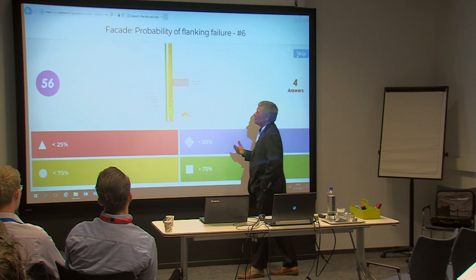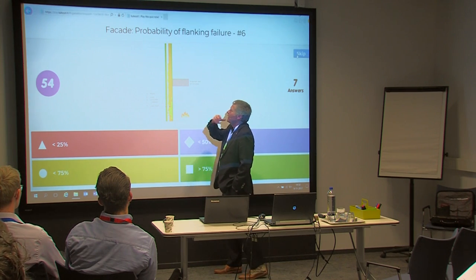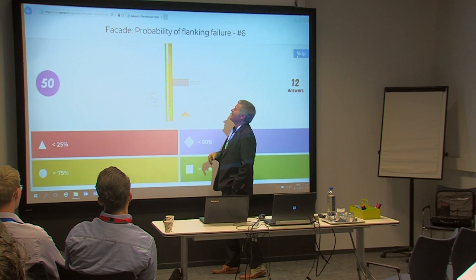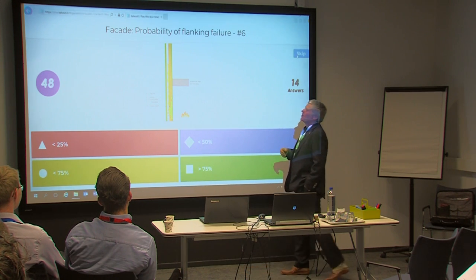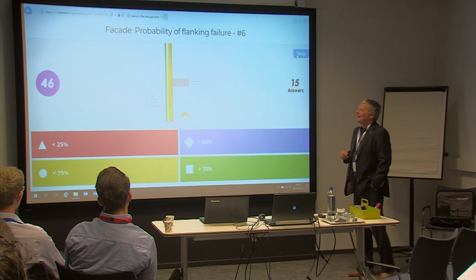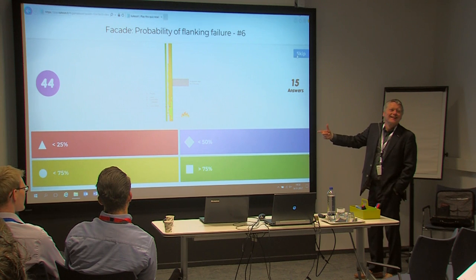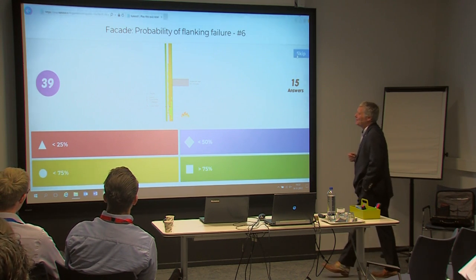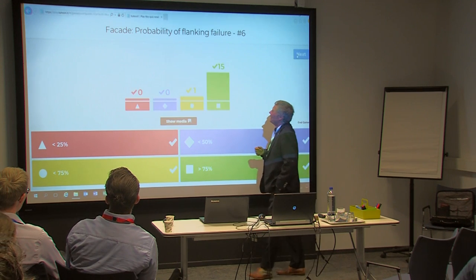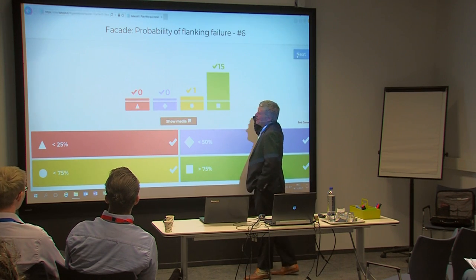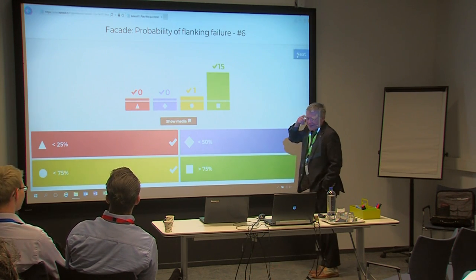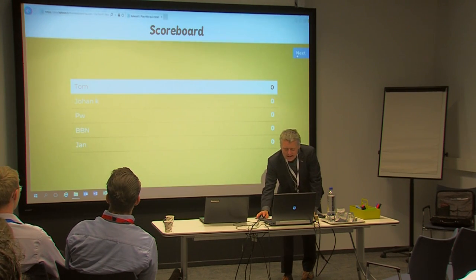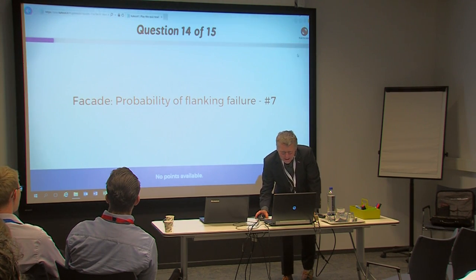The sixth facade detail is the same cavity construction but with combustible material layers. The flames in the diagram suggest flame spread possibilities. Results show a large failure probability, which was the expected answer.